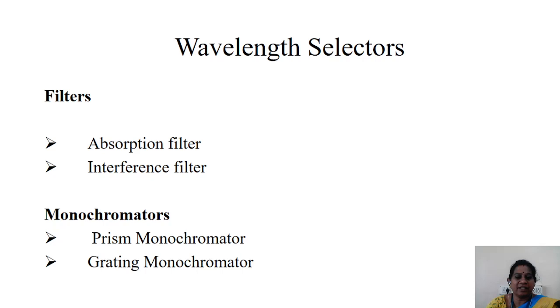So what are wavelength selectors? Wavelength selectors are devices which are used to select a particular wavelength, and when it comes to wavelength selectors you have two types: one is the filters and monochromators. Filters are used to remove the unwanted wavelength or allow only a particular wavelength to pass through.